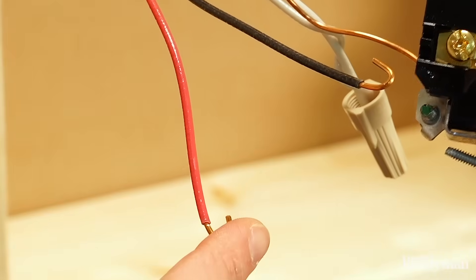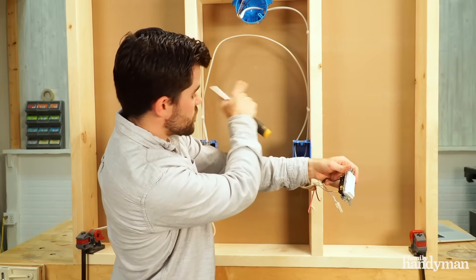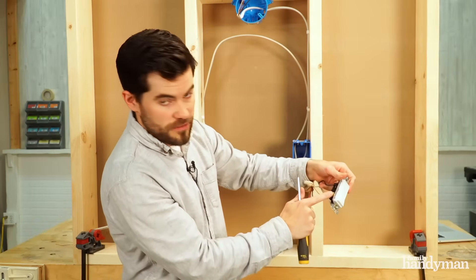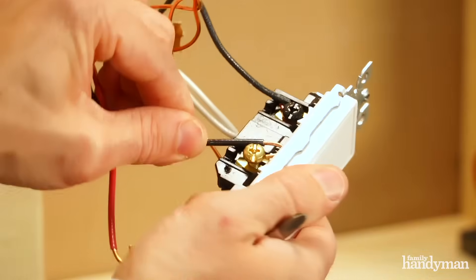Then the black and the red wire on the cable between the two switches gets attached to the traveler terminals on either side of the switch.